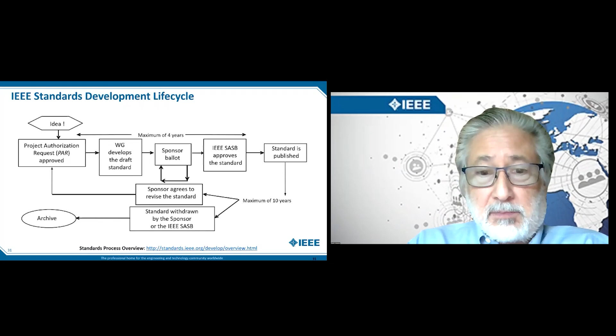This is a little dated, but these were some of the original drivers for 1547, and there will always continue to be requirements to cease to energize, galvanic separation without separation means, without an actual physical switch separating that PV system or vehicle-to-grid from the grid. The fear is if the grid goes down, the system could be in a configuration that allows a DER to backfeed through the transformer and energize the utility's distribution. If the utility thinks the system is down but DER is backfeeding it, that can be a safety hazard. So a core aspect of 1547, the original one, the revision, and going forward, will always be maintaining anti-islanding, meaning you don't want unintentional islanding of DER backfeeding and energizing the grid.